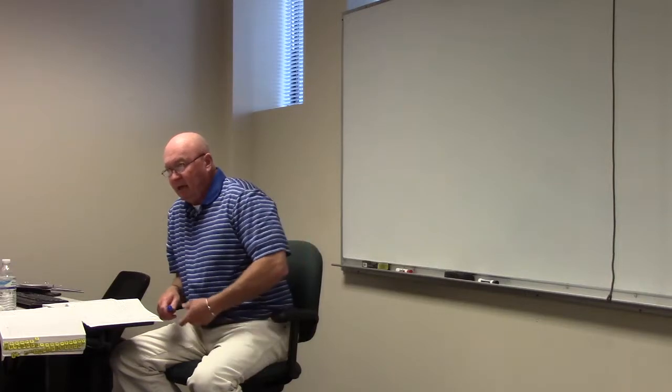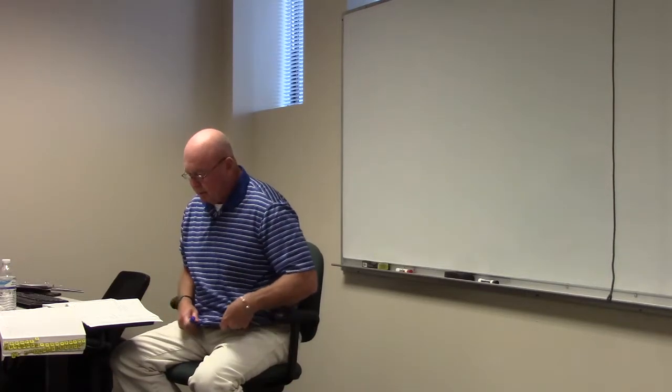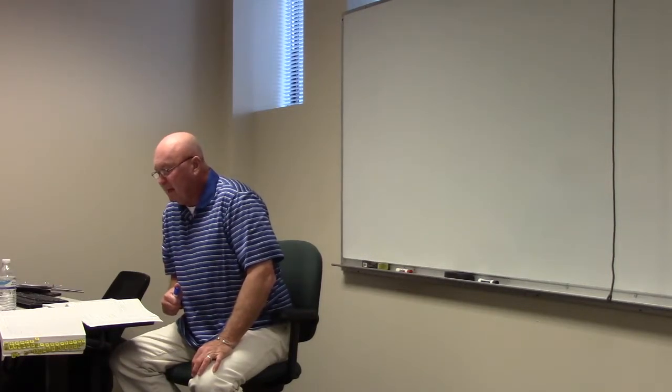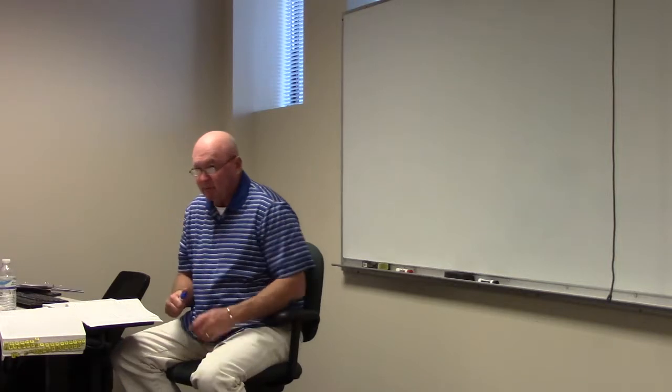We got to find out how many amps of 5 horsepower. 5 horsepower, 208 is how many amps on 430.250. 16.7. 16.7, as you can see there in our book on figure 10, that's what we got, is 16.7, no neutral. Okay. All right, the next thing, we have to take 25% of the largest motor.